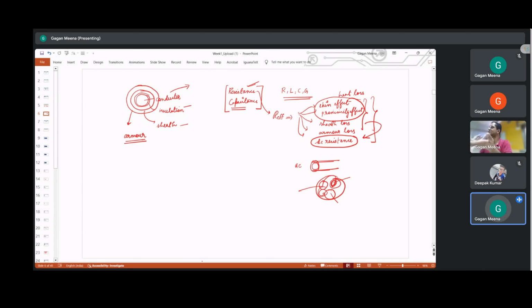Then we have sheath loss. In the sheath, because of current, we have the conductor and above that the sheath, with air in between, so it acts like a transformer. Just as in a transformer we have eddy current losses and hysteresis loss due to induced EMF, here also similar kinds of losses are there in the sheath as well as in the armor. That's why these different types of losses are there.